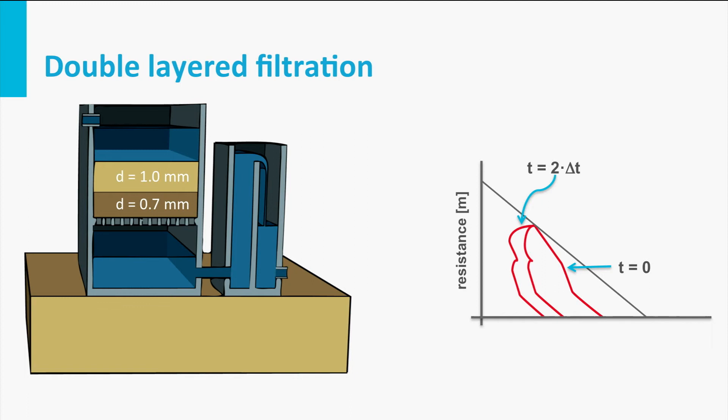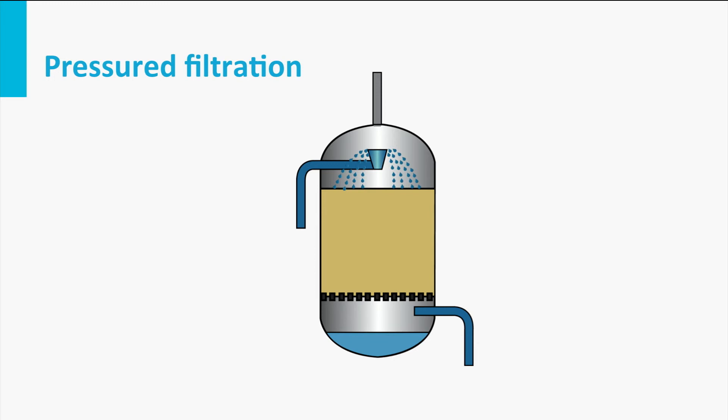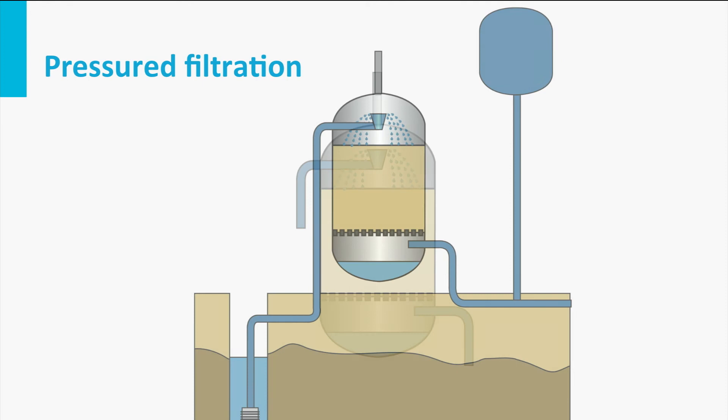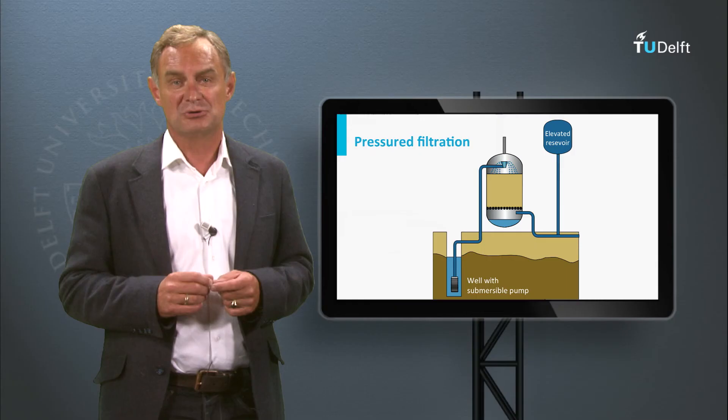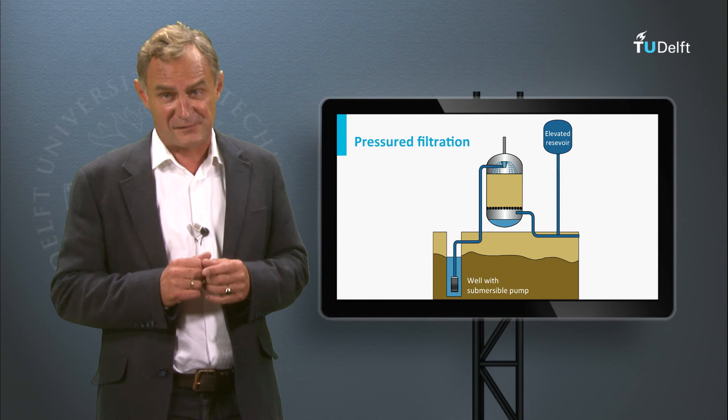Pressure filters are frequently used in industry because of their flexibility and the possibility to maintain high filtration velocities and long filter run times while keeping the grain size small. This is achieved by increasing the pressure on the filter. Water can even be pumped directly through the filter to an elevated water storage. However, a drawback of pressure filters is their sensitivity to filter troubles.